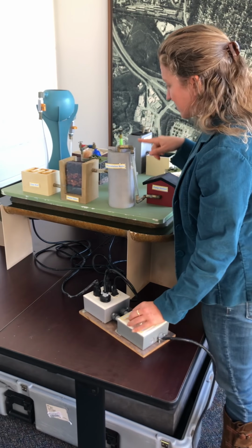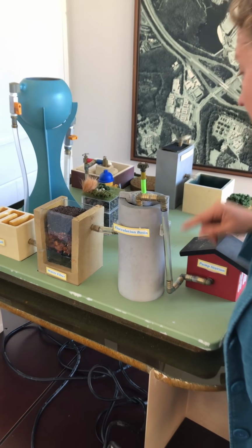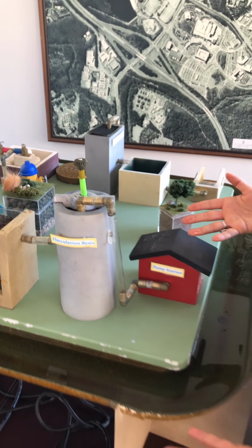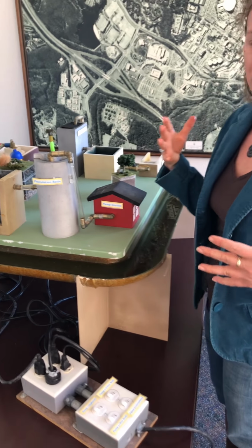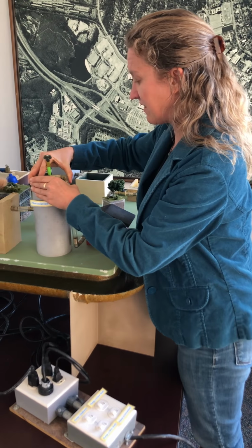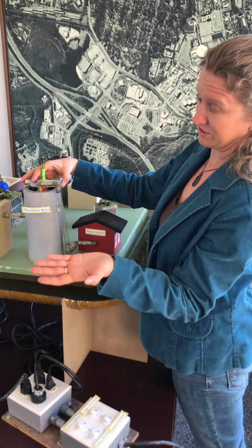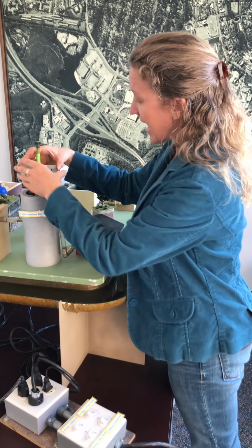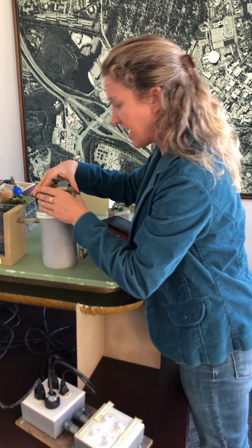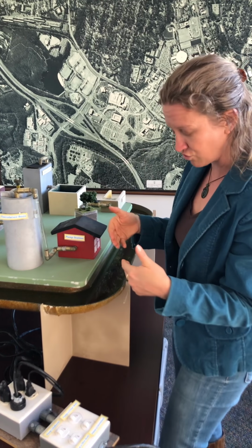And the first step is it goes into what we call a flocculation basin. So I want to stop it or else it might overflow. And what's happening in the flocculation basin is that we're going to try to drop out some of the sediment. So there's usually something that is added, which causes a coagulation. So you add a coagulant, and then there is usually something that turns inside to mix it all together until the sediment gets large enough and drops out.